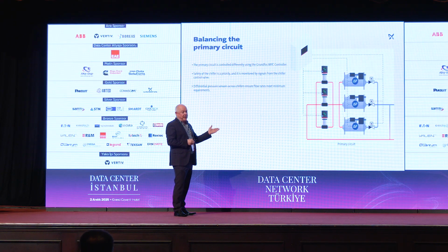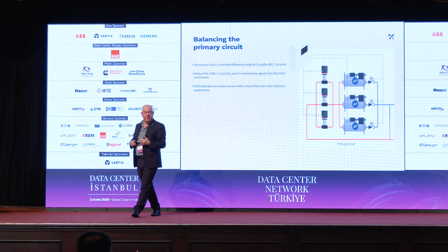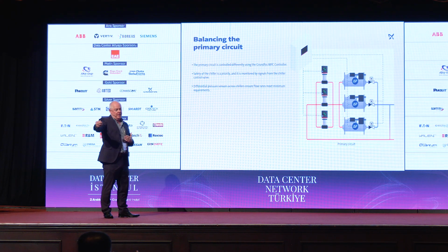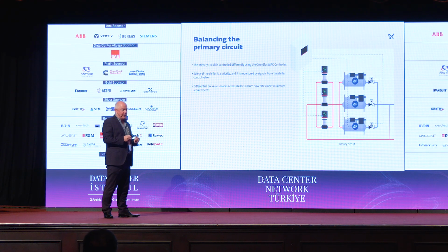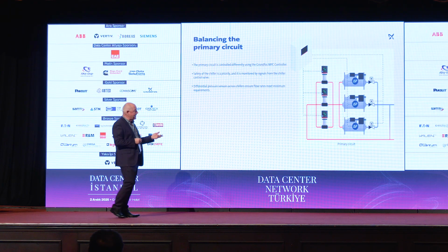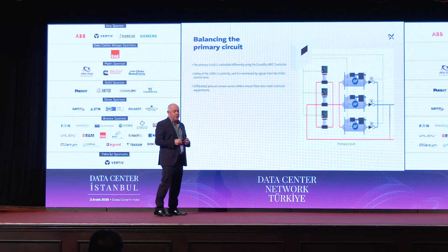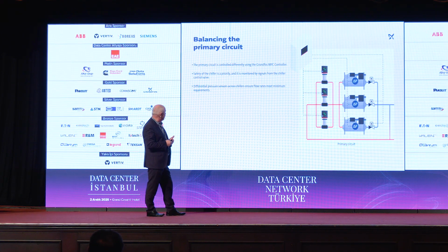When we have a load come on, the chiller will come on and we will check the flow rate across the circuit through differential pressure sensors. So if the demand is less than the minimum flow of the chiller, we'll make sure that we have the minimum flow going through the chiller. And in that case, we will have flow in the decoupling line, but it means that the chiller is saved and we don't end up destroying the chiller.